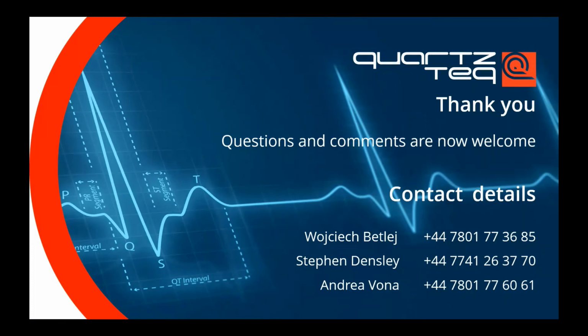Just to give you an example, we had a contract where the OEM condemned the machine. They said to the customer that you need to buy a new rotor because this one has to be scrapped. And yet, through big engineering work and study, we managed to recover that rotor within a few months. The machine is up and running, and it's been running for the last 4 years, if I remember right.